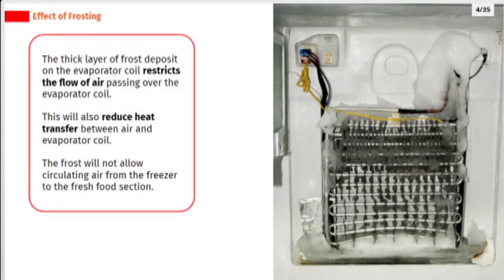The thick layer of frost deposit on the evaporator coil restricts the flow of air passing over the evaporator coil. This will also reduce heat transfer between air and evaporator coil. The frost will not allow circulating air from the freezer to the fresh food section.